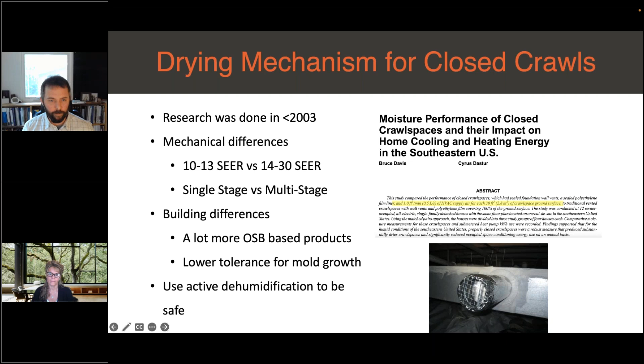So you can use supplemental dehumidification per the IRC. What I think is interesting is if you take that same strategy from inside the house, with how high the RH gets, and put it below the home, you're not getting the AC runtime anymore that used to push cooler, drier air into an already cool space, which drives the RH up alone. We just don't get the runtimes we used to when that was initially part of code. Great point—reduced runtimes mean lower latent removal by the HVAC system.